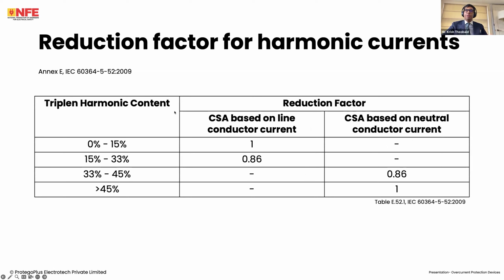Reduction factors for harmonic currents: between 0 to 15% harmonic content, we select the cross-sectional area based on the line conductor current and apply no reduction factor. Between 15 to 33%, we select it based on the line conductor current and apply a reduction factor of 0.86. Between 33 to 45%, also a 0.86 reduction factor. However, now we are selecting the cross-sectional area of the cable based on the neutral conductor current. In excess of 45% neutral conductor current, we do not need to apply this reduction factor anymore, because we have oversized it so significantly that the reduction means we will no longer utilize the line conductors to their full current carrying capacities, and that is offsetting the heat generated by the neutral conductor running at its full current carrying capacity.